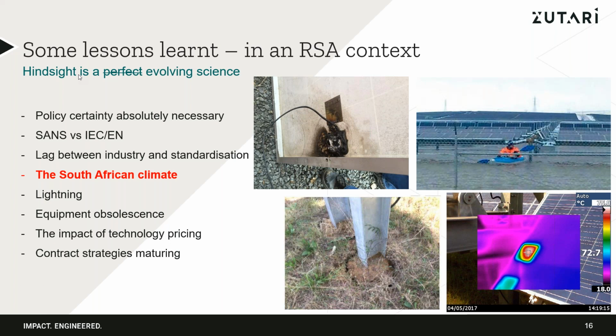Secondly, SANS versus IEC and EN. SANS is actually a very robust set of standards. It's been well worked over the years, and it knows South Africa's conditions very well. We found in many cases that the SANS standards are more stringent than IEC and EN, which are generally built on kinder environments. So when specifying in South Africa, remember SANS is a legislative requirement for some standards, like 10142, and it's important that reliance is not placed on European standards where a South African standard is available.